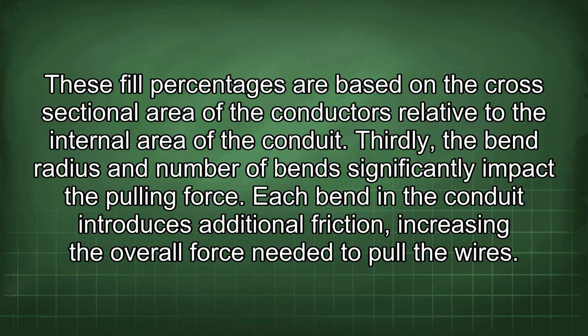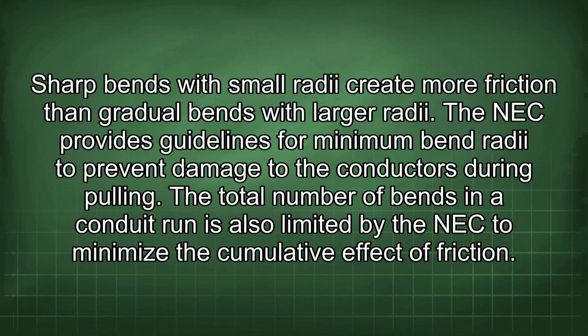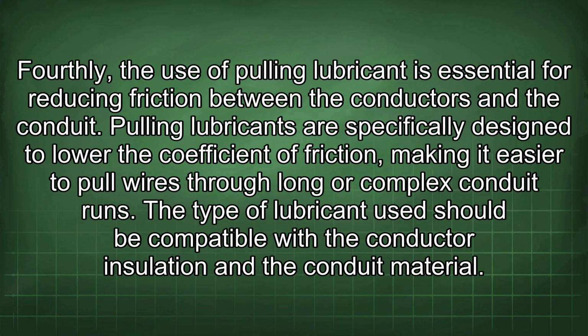Each bend in the conduit introduces additional friction, increasing the overall force needed to pull the wires. Sharp bends with small radii create more friction than gradual bends with larger radii. The NEC provides guidelines for minimum bend radii to prevent damage to the conductors during pulling. The total number of bends in a conduit run is also limited by the NEC to minimize the cumulative effect of friction. Fourthly, the use of pulling lubricant is essential for reducing friction between the conductors and the conduit.